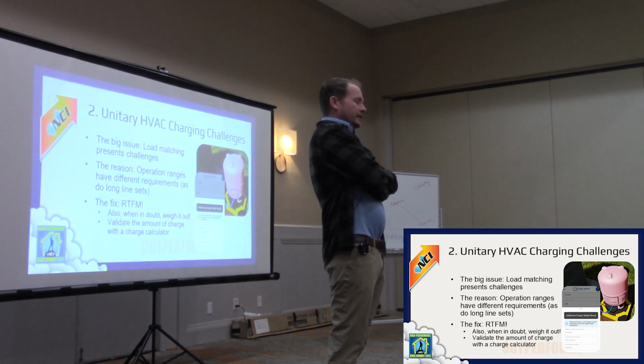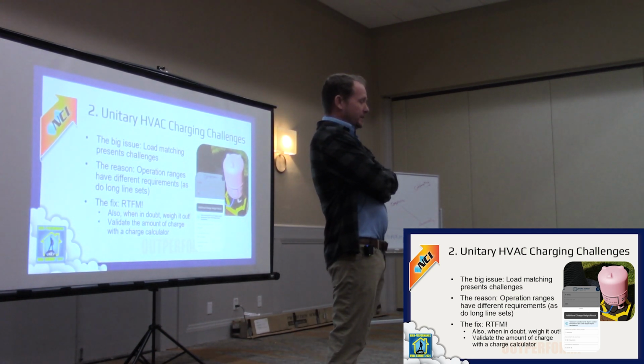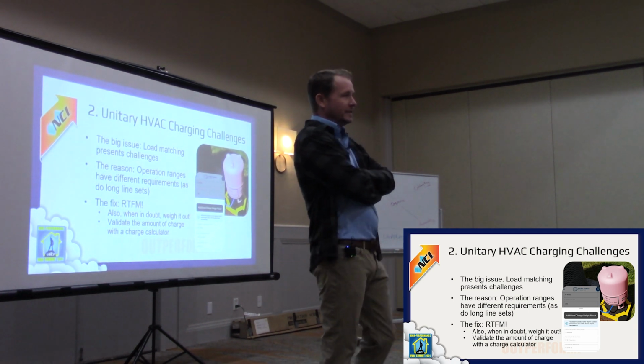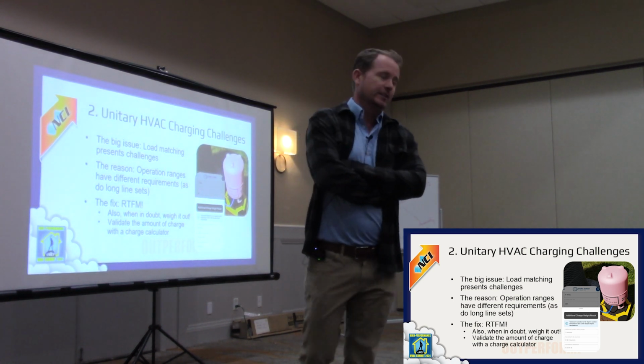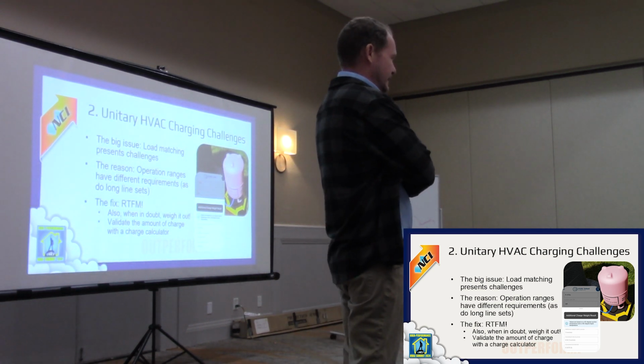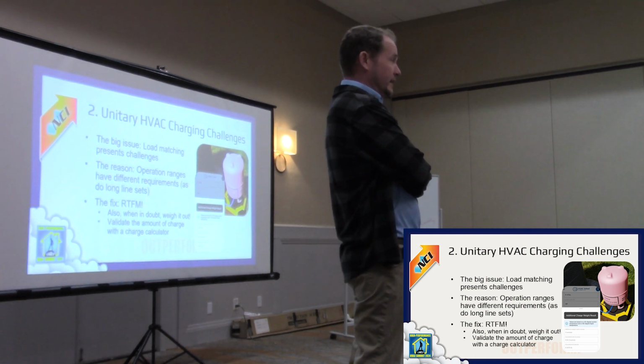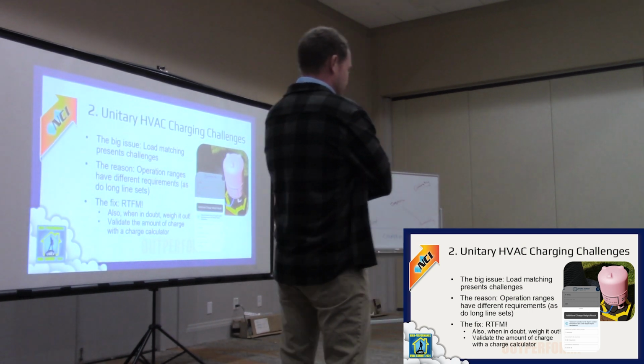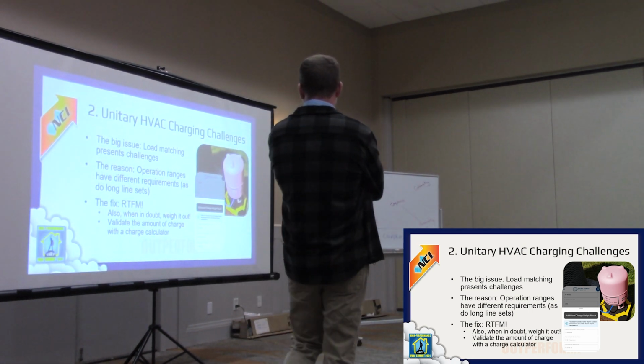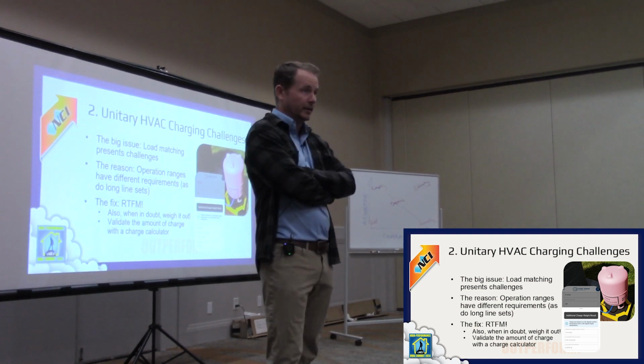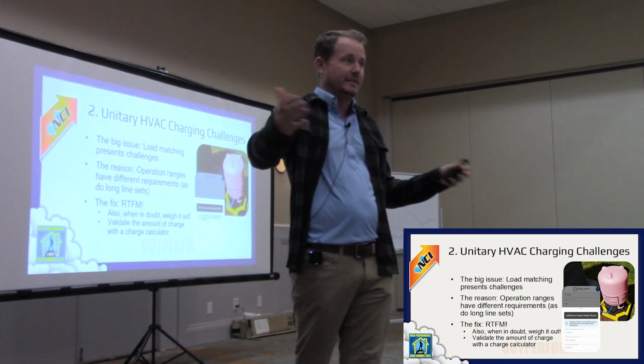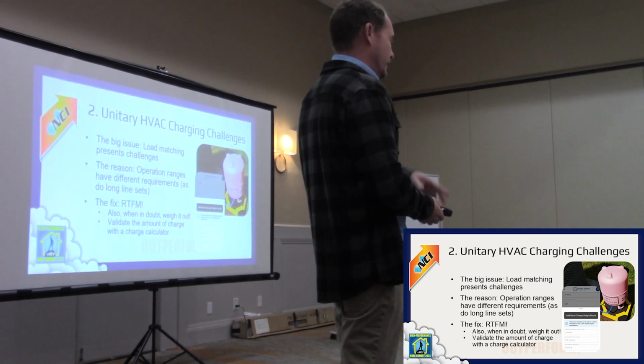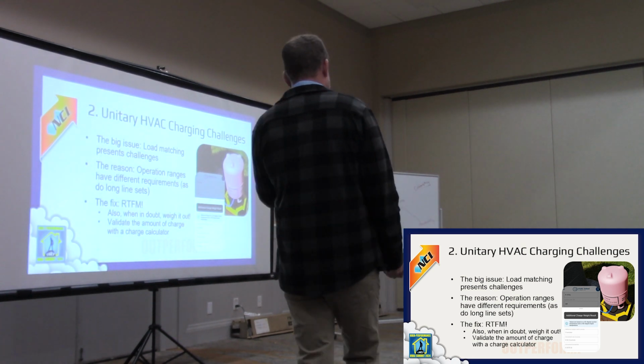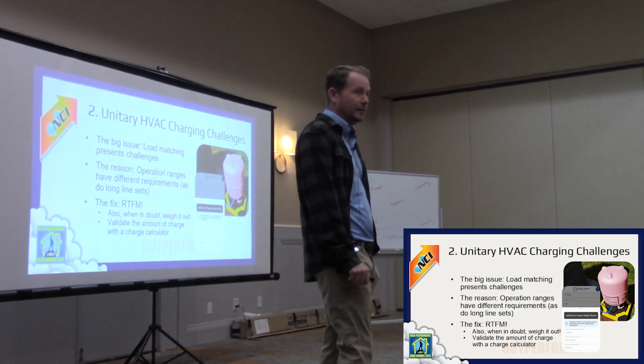So giving them some guidelines of what to go in is really important. The 0.6 ounces per foot of additional 3/8 is kind of a standard thing, but it's not always 3/8, so you have to adjust. I have a calculator on the HVAC School app where you put in your suction and liquid, and it compensates for both and tells you exactly how much to put in depending on the factory line charge - makes it easier for guys who struggle with math.